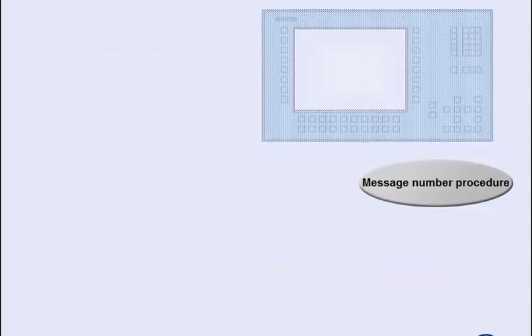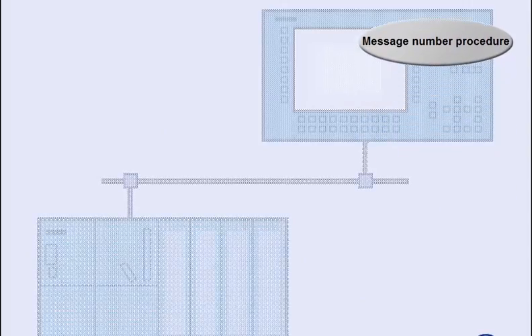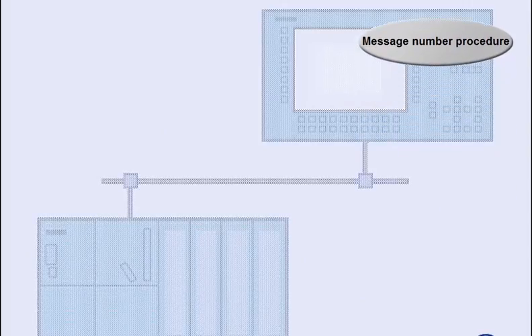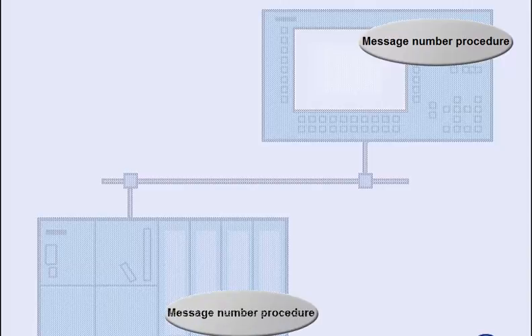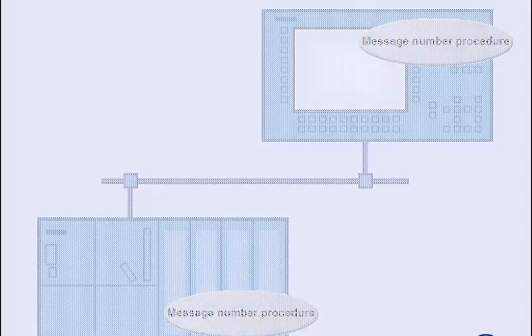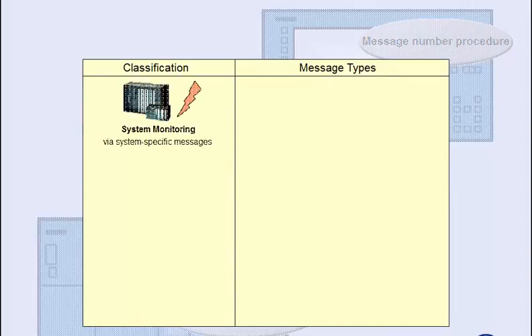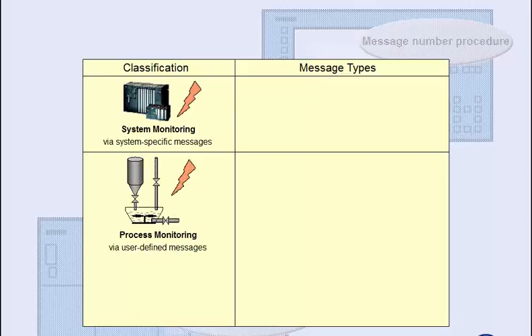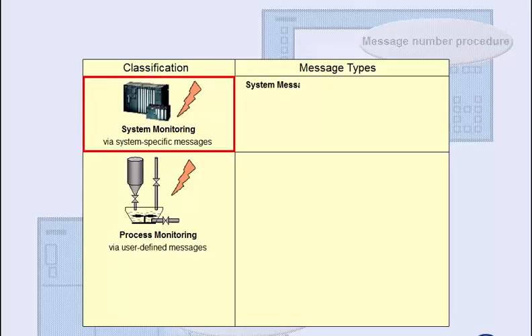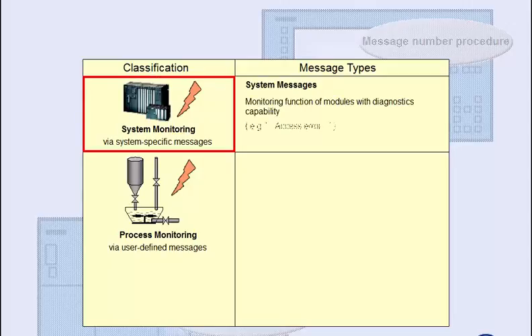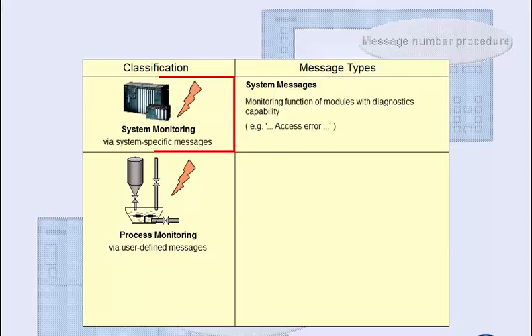In the message number procedure, the automation system assumes all reporting tasks, which has a number of decisive advantages. Two classes of messages are available. System-specific messages for system monitoring, and user-defined messages for process monitoring. Diagnosable modules are able to trigger system messages if required. The texts of these messages are predefined in the system, and correspond to specific events, such as an access error.